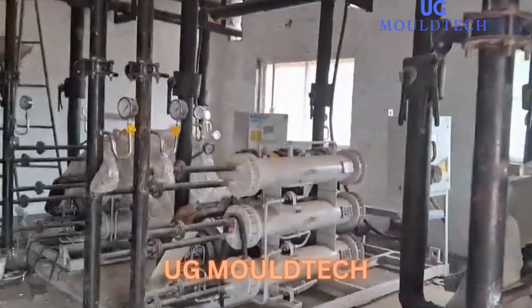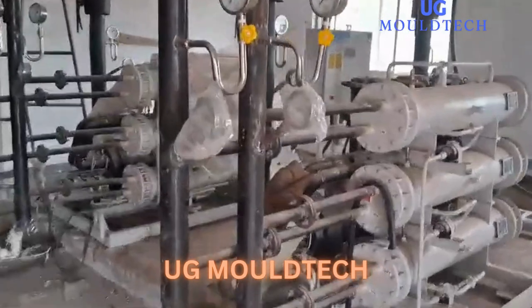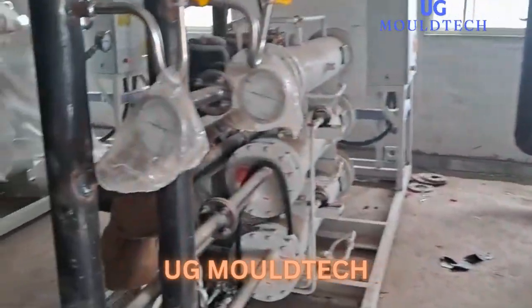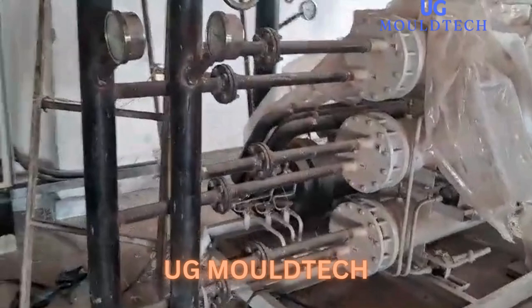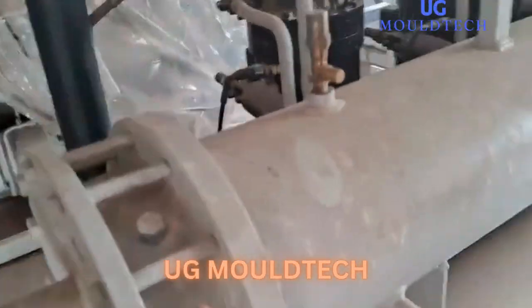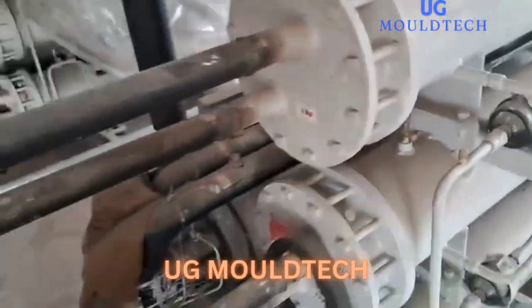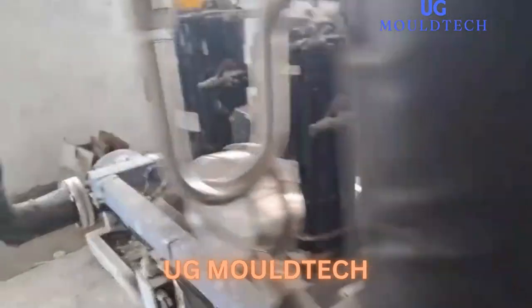Hello friends, welcome to our channel UG Mouldtech. Today we came to our process plant. This is the chiller plant. We are installing three chillers of 30 TR each — this is the make of Voltas. Two will be working and one will be standby. This is the condenser — you can see three condensers. And this is the chiller, or you can say evaporator. Three scroll compressors are used for cooling.